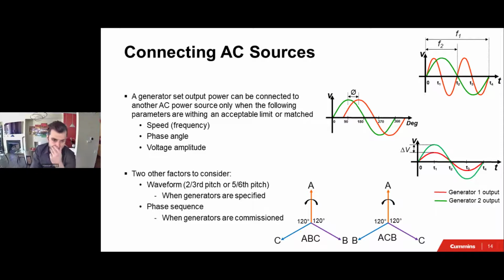And then the voltage amplitude difference between the two should also be kept to a minimum, say plus minus 5% or 10%. If we don't do that, the one with the higher potential, for example in here, you can see that at this angle right here, the green wave is at a higher potential, or at T1 in here, the green wave is again at its max. The one with the higher potential is going to push the one with the lower potential, right? So then you're going to have pushing current, or push the other source around. And this is why I want to keep that to a minimum.